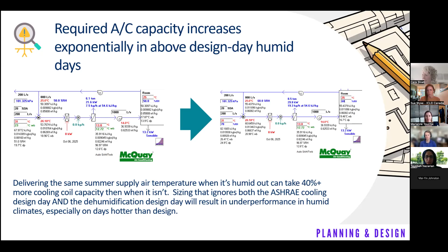And this next slide speaks to one of the reasons we get in this trouble, which is that we are actually worried about oversizing cooling systems. When we oversize them, we get short cycling on compressors, which reduces their life cycle. We get poor humidity control in most conditions because we can't actually run the coil for long enough to get the temperatures down. We get uneven temperatures.